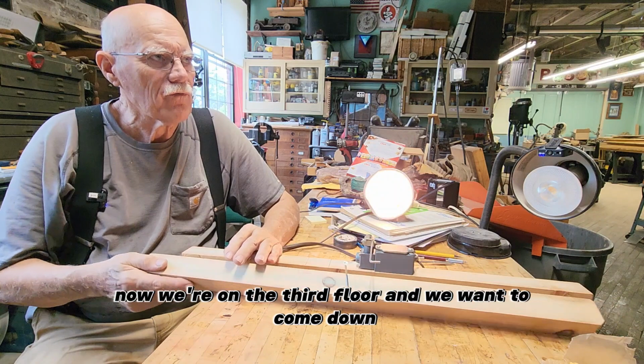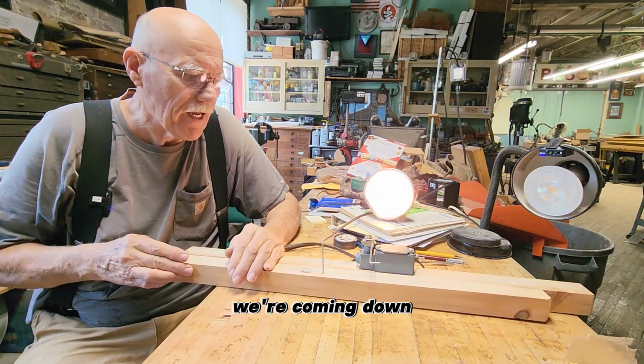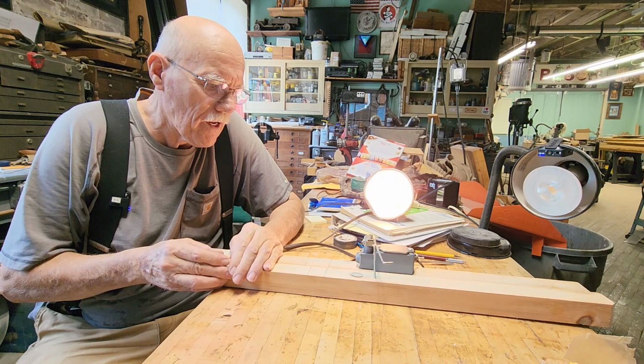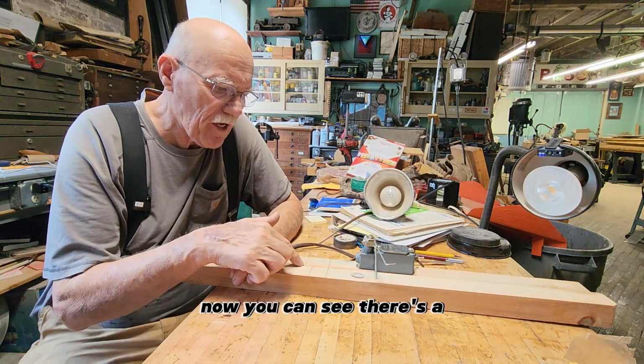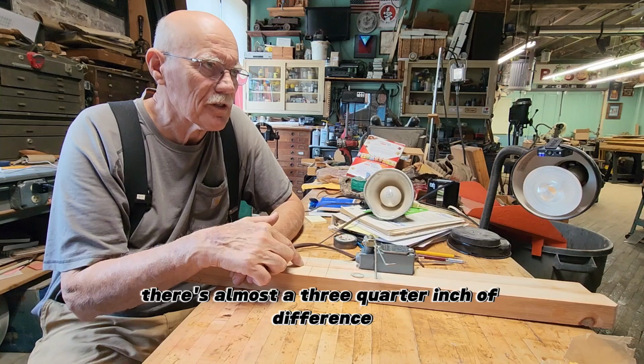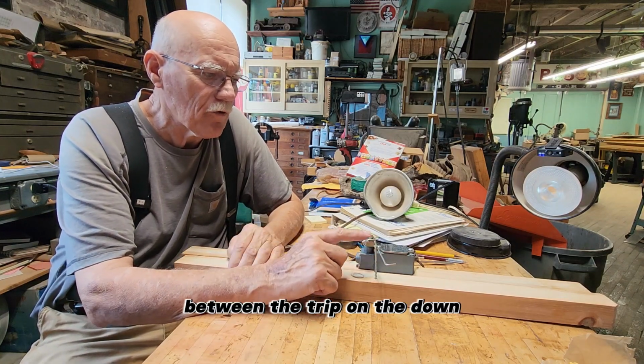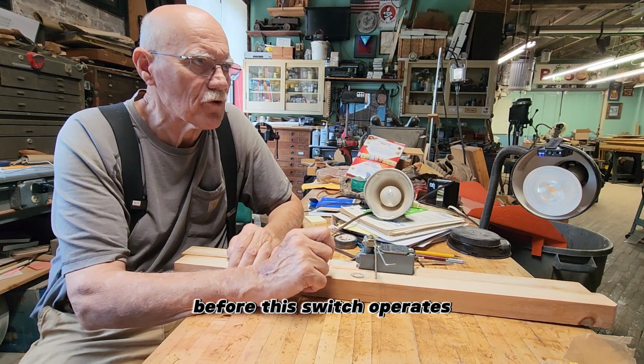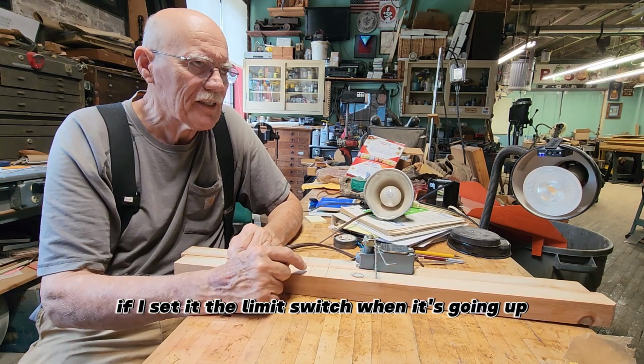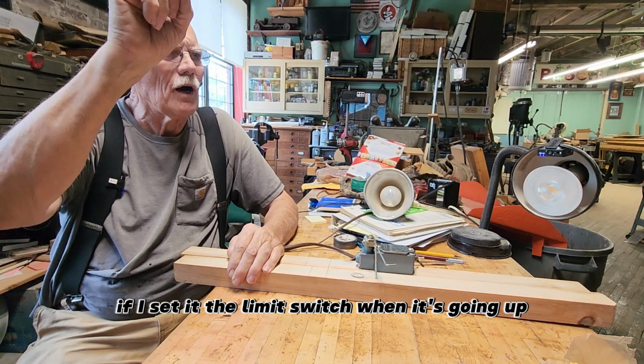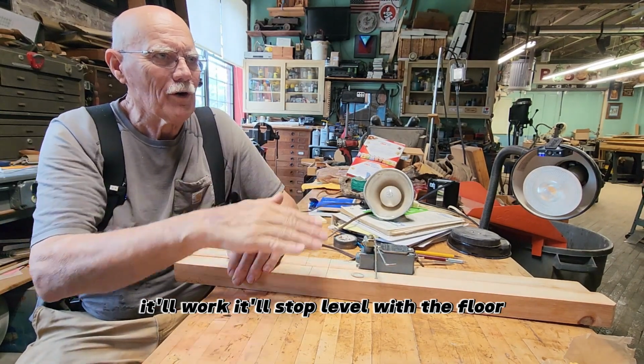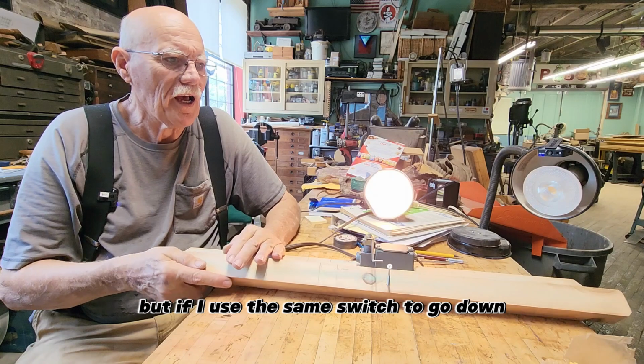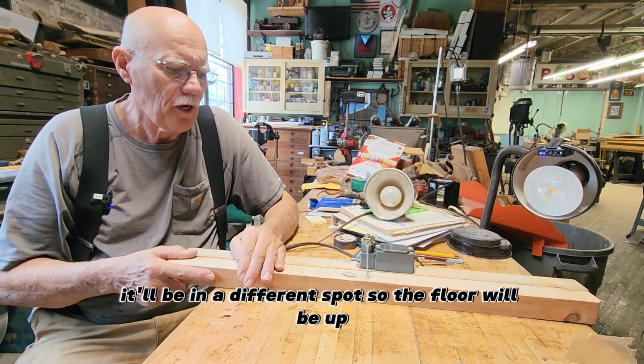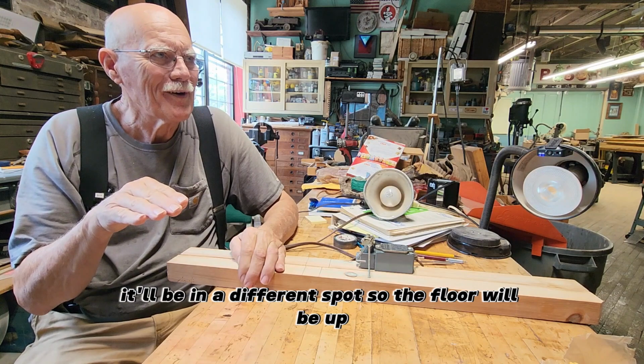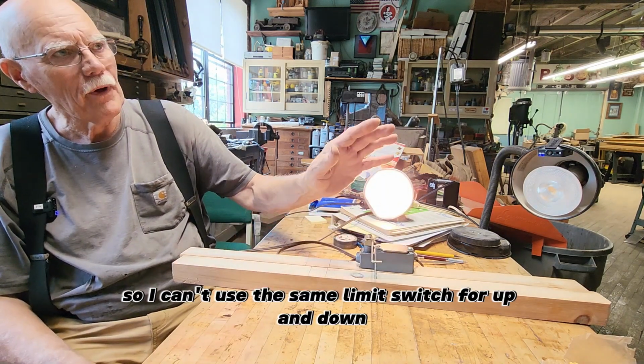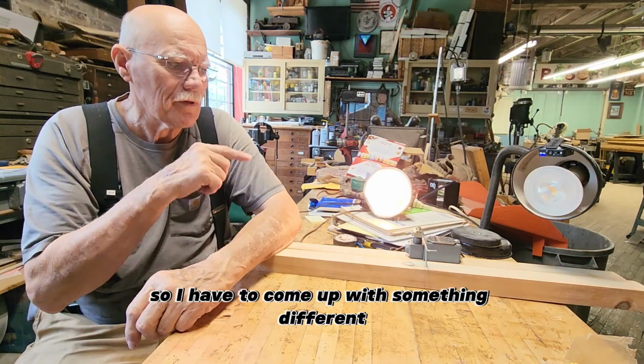Now say we're on the 3rd floor, and we want to come down. We're coming down, we hit the switch. Now you can see there's almost a 3/4 inch difference between the trip on the down. It's about a 10-degree angle before this switch operates. If I set the limit switch when it's going up, it'll stop level with the floor. But if I use the same switch to go down, it'll be in a different spot. So the floor will be up. So I can't use the same limit switch for up and down. So I have to come up with something different.